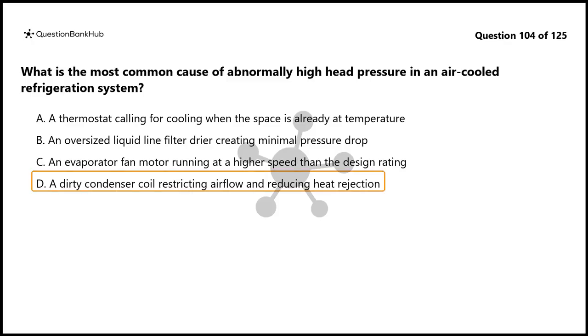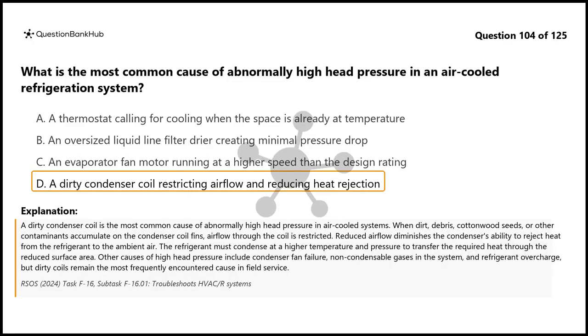The correct answer is D. A dirty condenser coil is the most common cause of abnormally high head pressure in air-cooled systems. When dirt, debris, cottonwood seeds, or other contaminants accumulate on the condenser coil fins, airflow through the coil is restricted. Reduced airflow diminishes the condenser's ability to reject heat from the refrigerant to the ambient air. The refrigerant must condense at a higher temperature and pressure to transfer the required heat through the reduced surface area. Other causes of high head pressure include condenser fan failure, non-condensable gases in the system, and refrigerant overcharge, but dirty coils remain the most frequently encountered cause in field service.